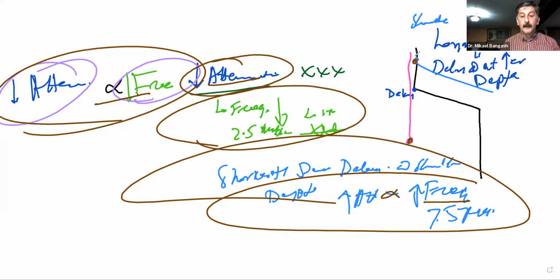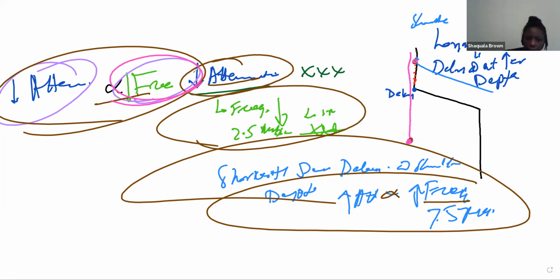Did that make sense? That would mainly mean that those reflections are returning from a shallower depth, compared to a low frequency transducer, which wouldn't start to have more compensation as early; more compensation will be required. But here the question asks which transducer is going to have the longest delay, which means that the delay is going to be at the greater depth. That's going to be the sound that is less attenuating. Where do you get that from? A low frequency transducer. Did that make sense?